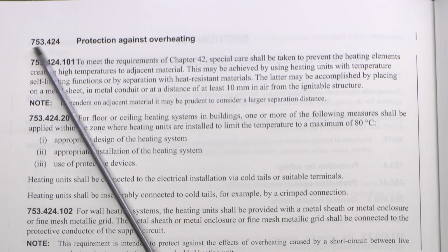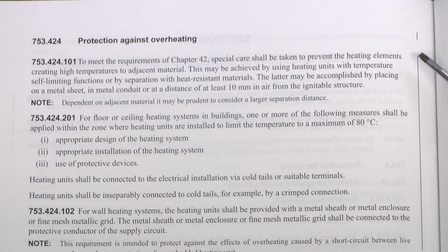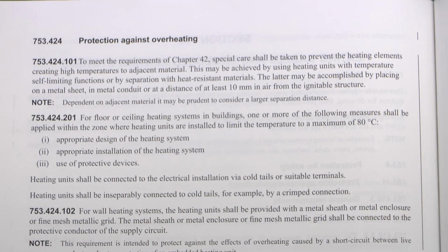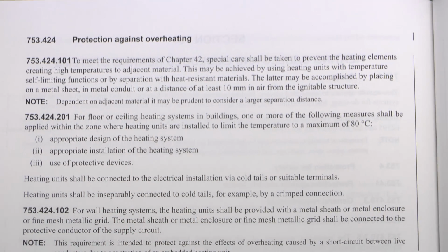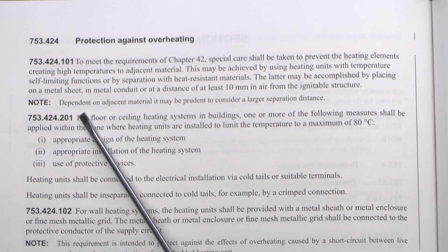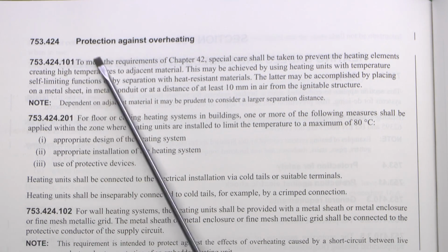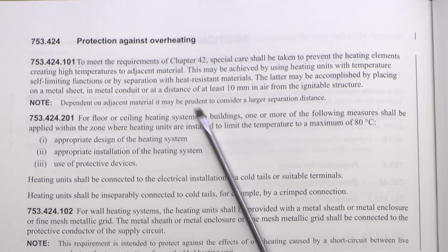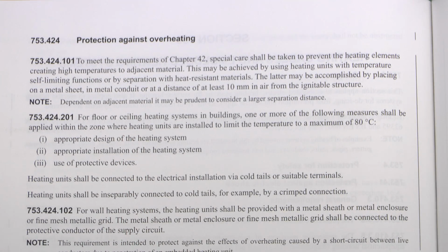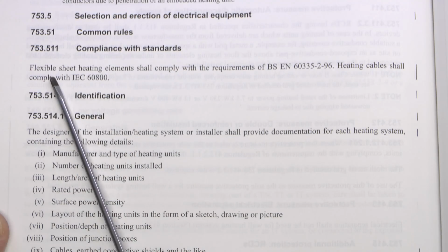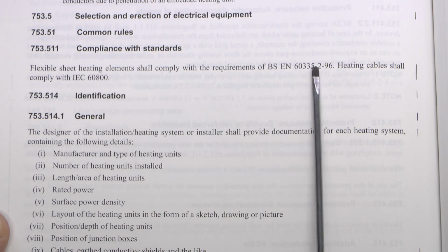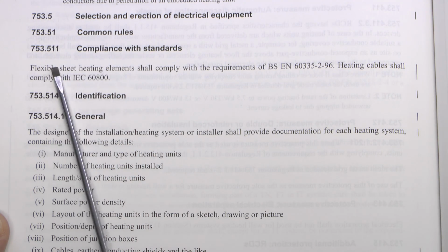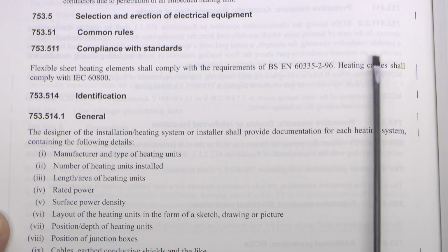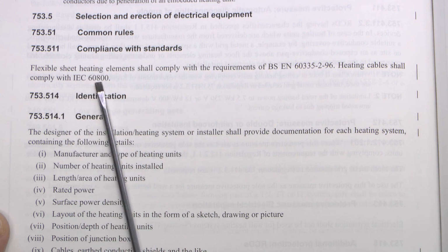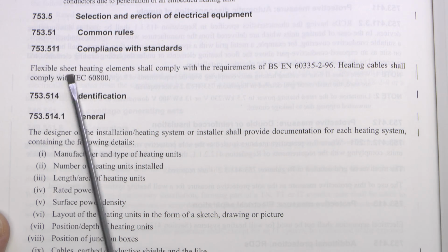This section here, 753424, protection against overheating. Although it's marked as all new, most of this has been rearranged and rewritten. These are actually new numbers here, the 101 and the 201, but the content is basically what was here previously, just changed around. Now this one, 753511, has been expanded into two items, so now we've got flexible sheet heating elements shall comply with this standard, and heating cables shall comply with this. Previously it just referred to the flexible sheet heating elements and cables were not mentioned.